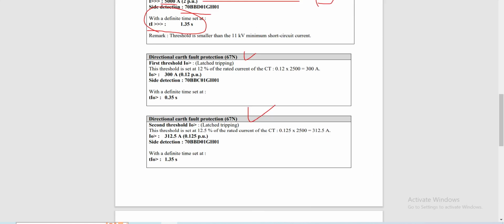Our first threshold is set at 12% of the rated current of the CT, which is 2,500 ampere times 0.12. That's why we have 300 ampere. So for our earth fault protection, the first threshold is set at 300 ampere, at 0.12 per unit. The time setting is a definite time of 0.35 second.